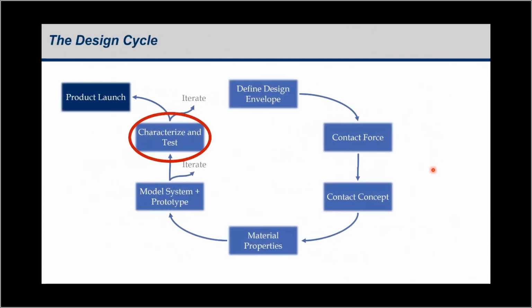So that's the type of characterization that we'd do ahead of time to say, well, should you even enter into a test cycle? So go through a characterization. If you go through characterization, that can then launch you into your test cycle if you like the results. If not, you iterate back, because usually we see in durability testing, the resources and the cost of durability testing is much higher than, say, the cost of characterization. And also the time to characterize is usually shorter than the time to do durability testing.